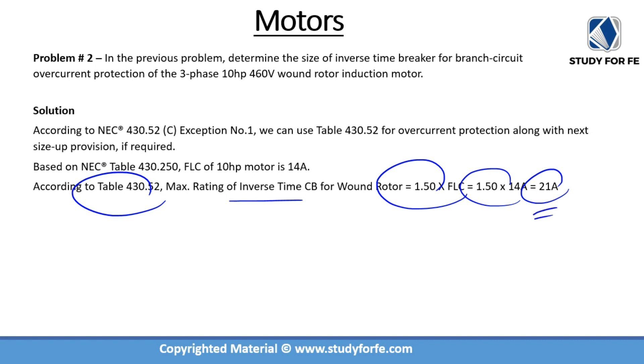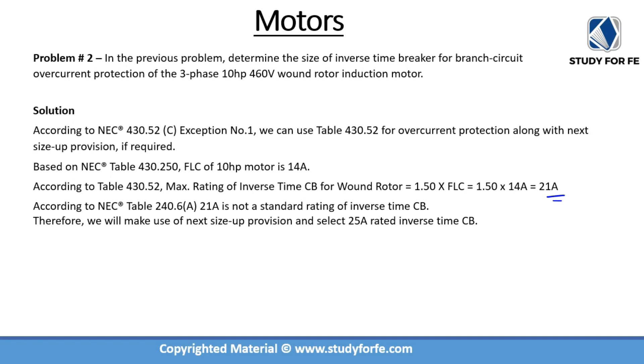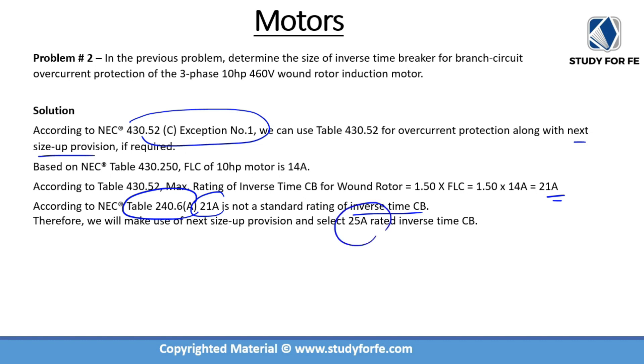We've established the maximum allowable OCPD rating using these two tables and the relevant code section. However, when we look at table 240.6(A), which lists standard ratings of inverse time circuit breakers, we find that 21 amps is not a standard rating. So we apply the next-size-up provision from 430.52(C) exception number 1 and select 25 amps. The answer is 25 amps, not 21 amps.